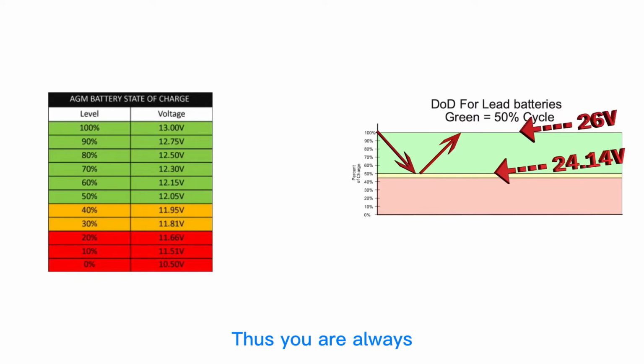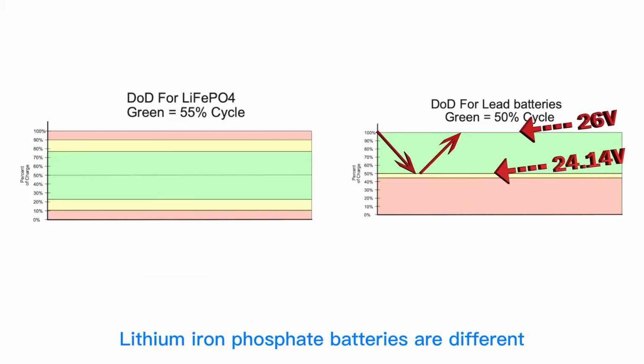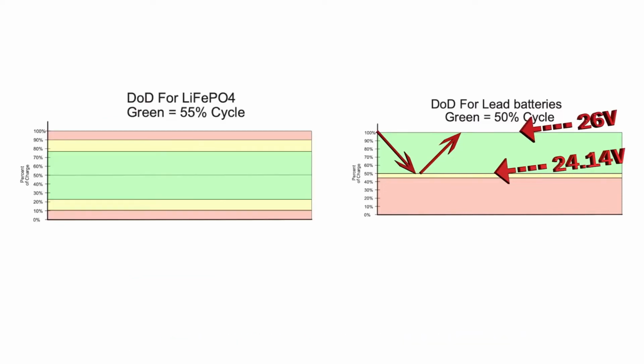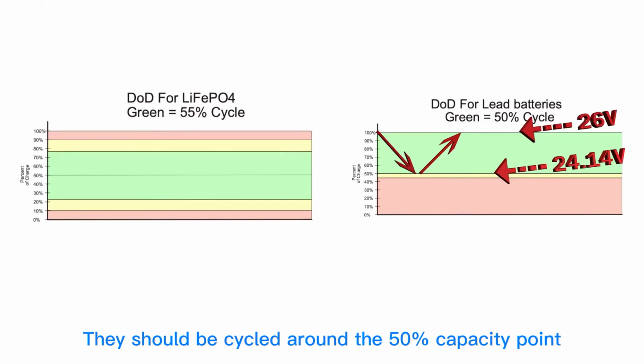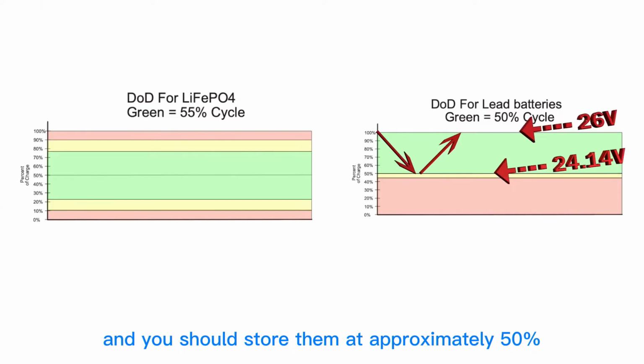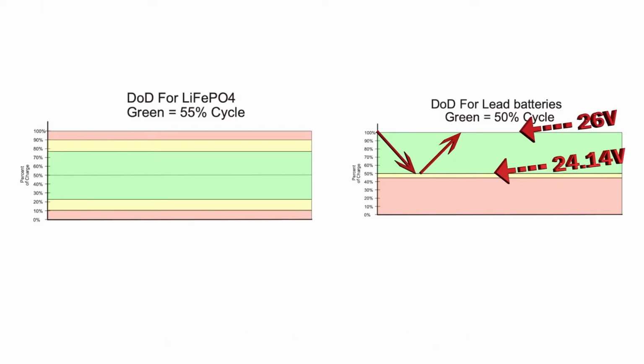Thus, you are always cycling an AGM battery at the top end of the voltage range. Lithium iron phosphate batteries are different. They like to be around 50% capacity, and they will last longer if you keep them close to 50%. They should be cycled around the 50% capacity point, and you should store them at approximately 50%.